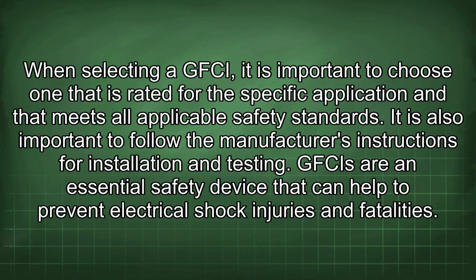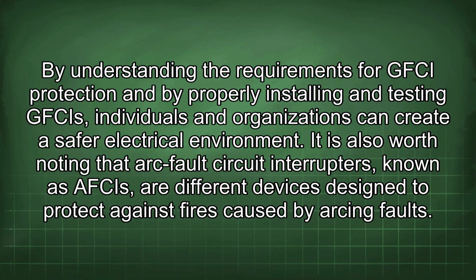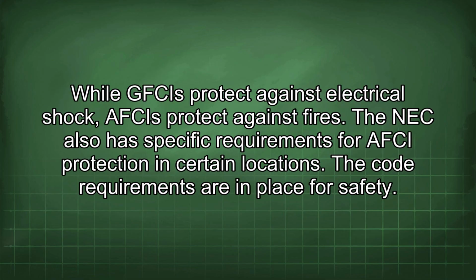When selecting a GFCI, it is important to choose one that is rated for the specific application and that meets all applicable safety standards. It is also important to follow the manufacturer's instructions for installation and testing. GFCIs are an essential safety device that can help to prevent electrical shock injuries and fatalities. By understanding the requirements for GFCI protection and by properly installing and testing GFCIs, individuals and organizations can create a safer electrical environment. It is also worth noting that arc fault circuit interrupters, known as AFCIs, are different devices designed to protect against fires caused by arcing faults. While GFCIs protect against electrical shock, AFCIs protect against fires.